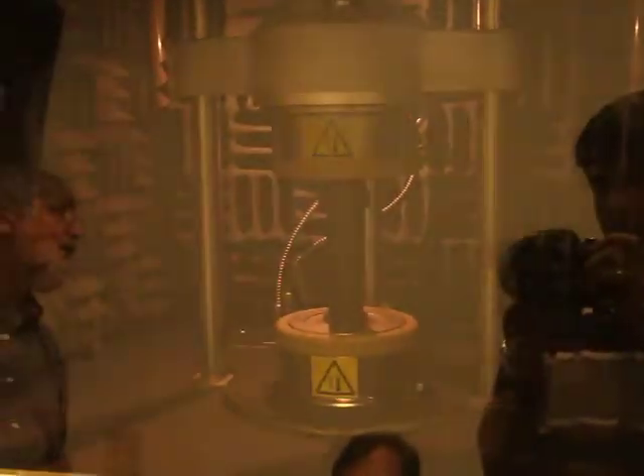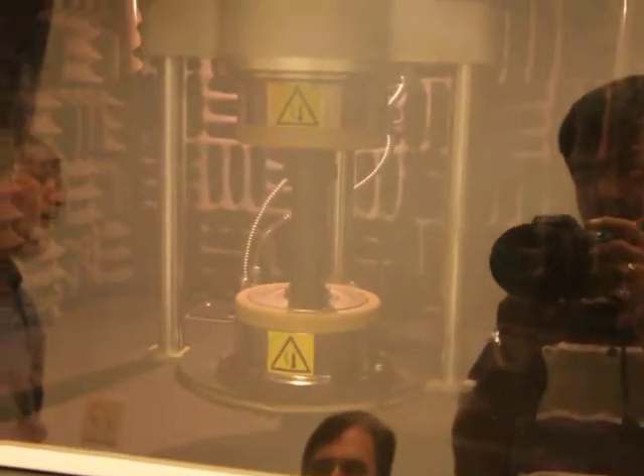How about the consistency of the rheometer? Based on your experience, between the same type of material, what is the consistency between runs? We will see essentially the same results on material, if the material is essentially the same. We've done it about three years later. Like the values, the viscosity value or G' value, is there any shift? No, no, because you're measuring torque basically. It's pretty constant. Now you will get a change if you get a little change in fiber volume or something like that, but that's actually representative of the material.